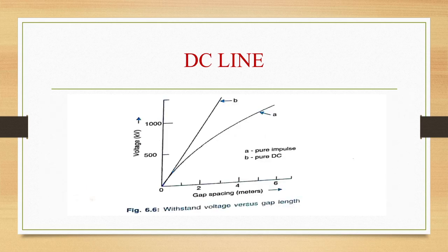There are special problems with direct voltage stresses on an insulator. The first problem is that of ion migration that will take place in the insulating material, which is a function of temperature. Insulating material should have very little ion migration even at high ambient temperatures. There can be thermal runaway due to the ionic conduction in a very narrow zone of the dielectric, which results in aging of the dielectric. Current that flows in the insulator body is dependent on the resistivity, which is a function of the temperature.